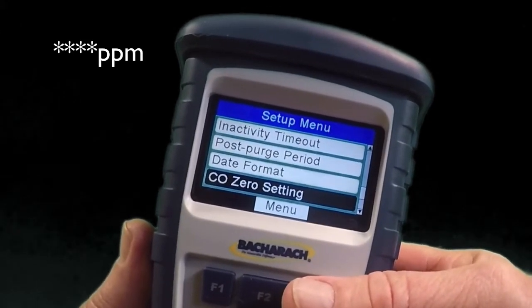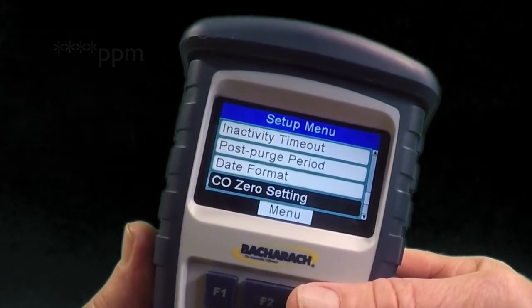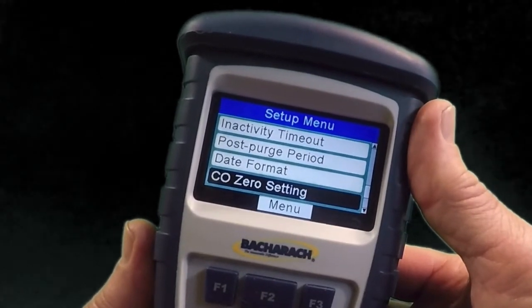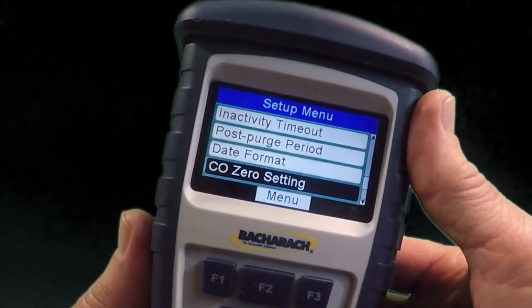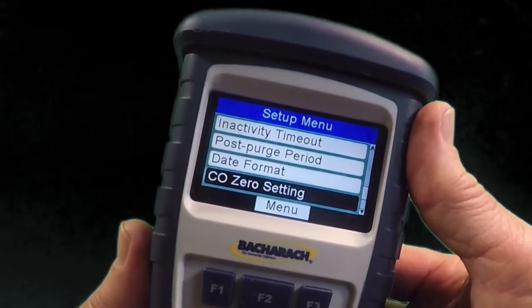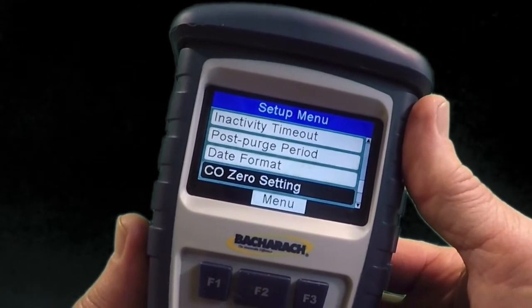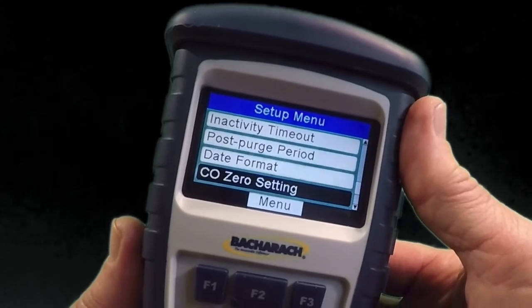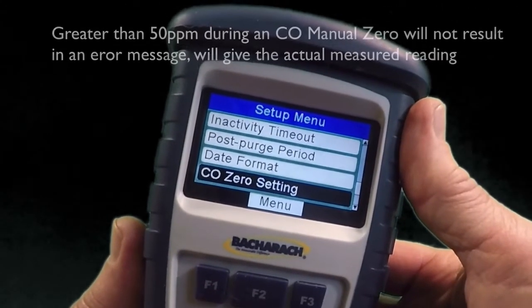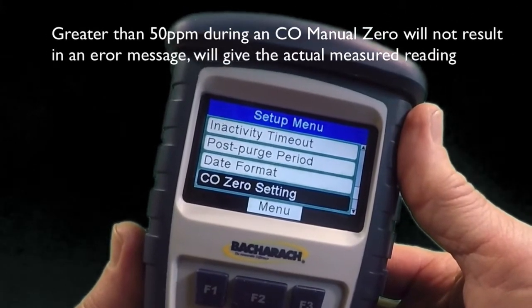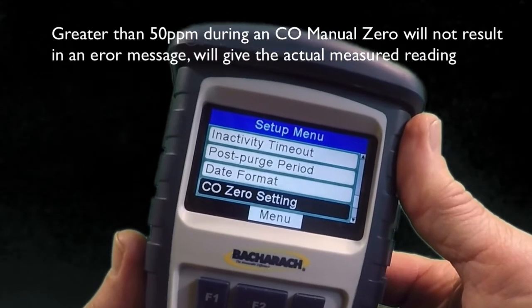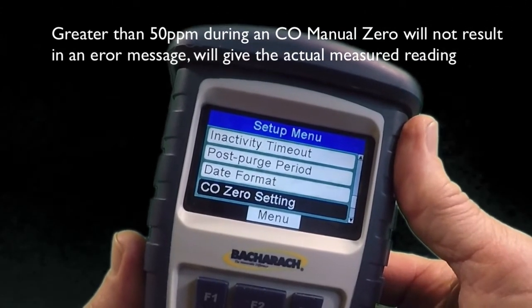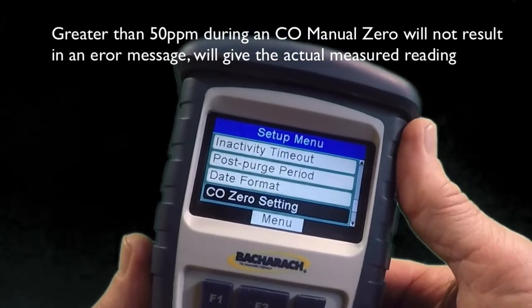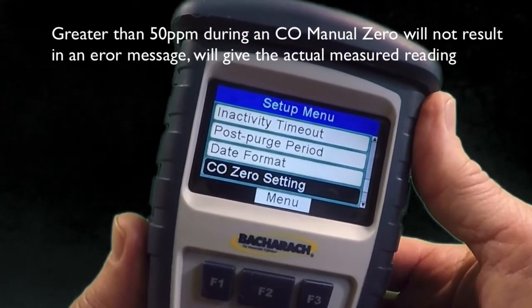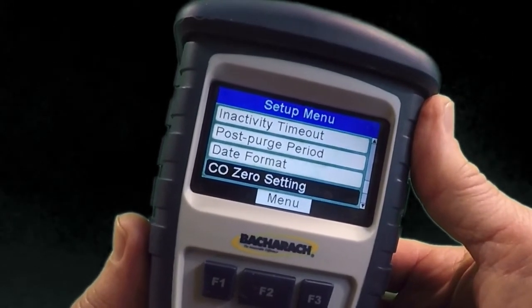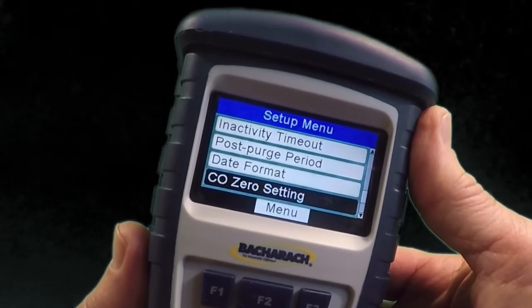Again, if this ever happens, you need to go to clean air, turn the instrument off, then on, and see what the display reads. If it reads 0, go back into the space and watch that carbon monoxide reading. If it's set up for a manual 0, there will be no error message. Instead, the run screen will display the CO level that it's detecting. So make sure that when you turn the instrument on, when it comes up to that run hold screen, you take a glance at that carbon monoxide level. Again, that's why I think it's a good idea to have that in the display.